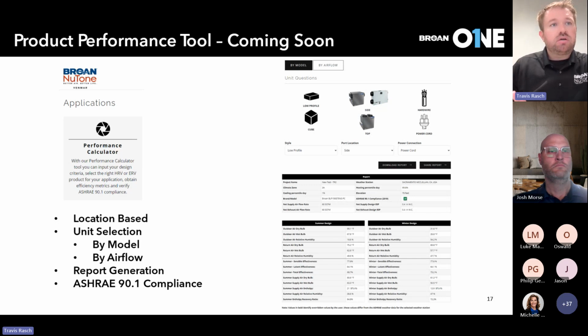Based on that location and unit selection, you're able to modify the airflows, both supply and exhaust, your static pressure, basically input any of those design criteria you'd typically need to specify this type of product. Ultimately you'll get a calculation report showing both summer and winter design conditions, all those values including effectiveness, latent, supply air dry bulb, wet bulb, enthalpy, and for ASHRAE 90.1 compliance, the enthalpy recovery ratio in both summer and winter design conditions.